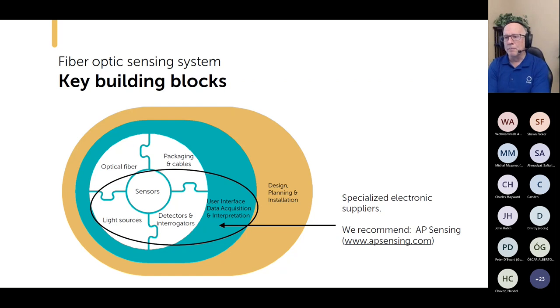So what you do is two things. First of all, you change the outer jacket from polyethylene to something that's flame retardant. You can't really make it flame resistant or fireproof. That's more like a metal cable, and even there, you're kind of limited. In today's environment, we don't like to talk about things as being bulletproof. We talk about them being bullet resistant, because somebody's going to build a bigger or more powerful bullet. So we just say it's resistant. It's the same with that outer jacket material, or with any cable, even a metal one. You can make it resistant, but you can't make it absolutely flameproof.